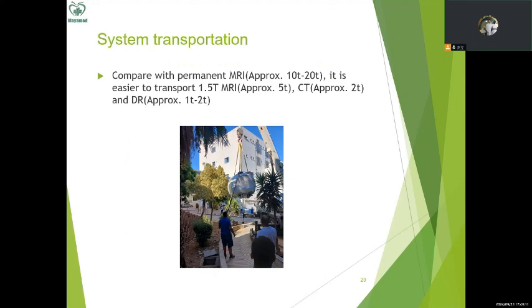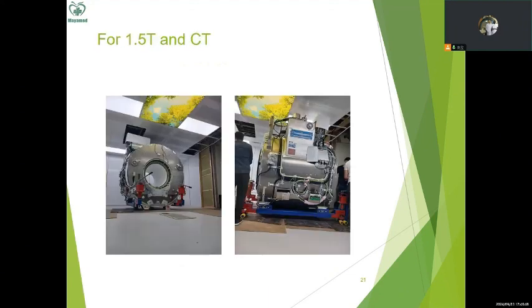So we just introduced the permanent MRI magnet, which is very heavy. And regarding the 1.5 Tesla, and also the CT and the DR, it is much easier compared with permanent MRI. That is because the 1.5 Tesla we just mentioned weighs approximately 5 tons, the CT is approximately 2 or 3 tons only, and the DR 1 to 2 tons only. So we simply use the crane to lift it up, and then we put it onto the unloading platform and move it, even just using the fork as in these pictures, to put it in the right position. That's it. That's all. So compared with permanent MRI, the other medical imaging equipment systems are quite easy to position.